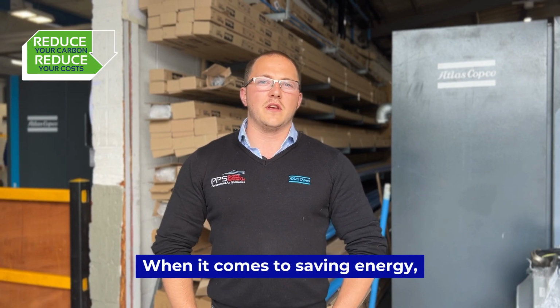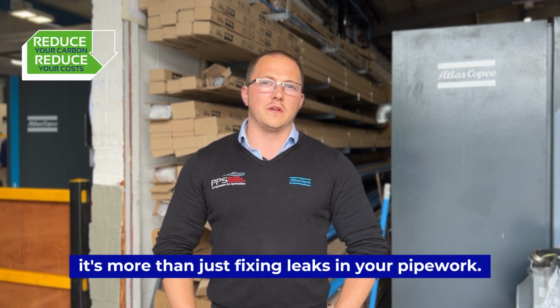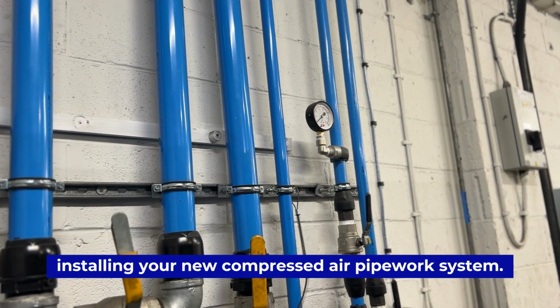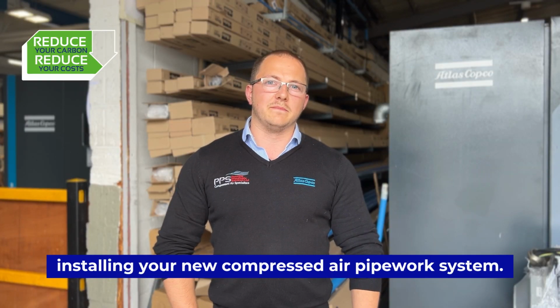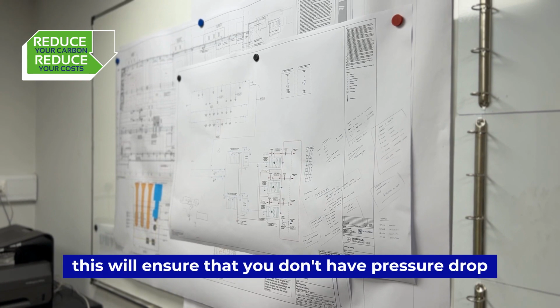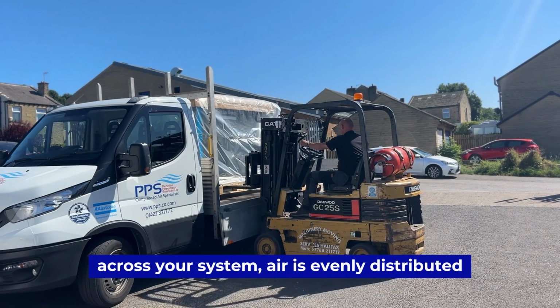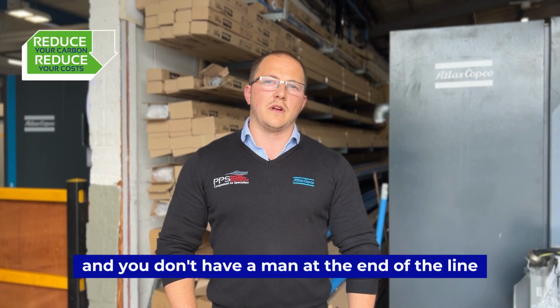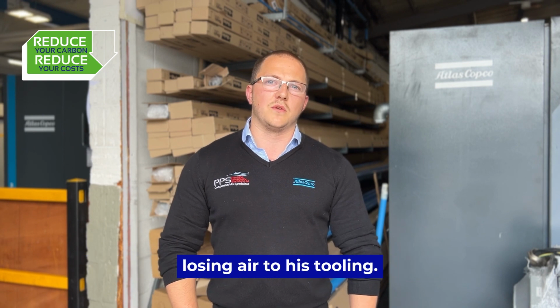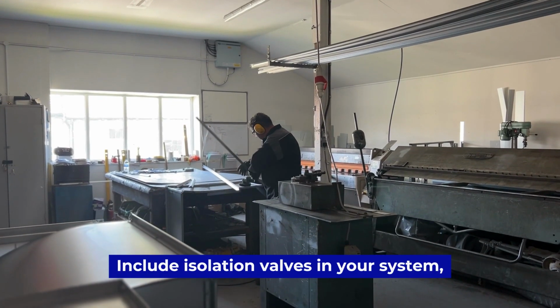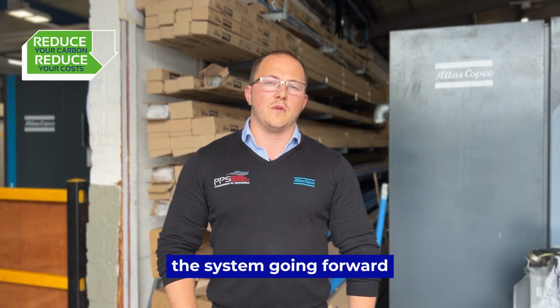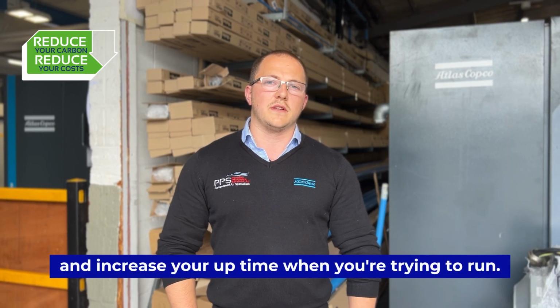When it comes to saving energy, it's more than just fixing leaks in your pipework. So let's have a look at some points to consider when installing your new compressed air pipework system. So firstly, create ring mains. This will ensure that you don't have pressure drop across your system, air is evenly distributed, and you don't have a man at the end of the line losing air to his tooling. Include isolation valves in your system. This will mean that you can modify the system going forward and increase your uptime.